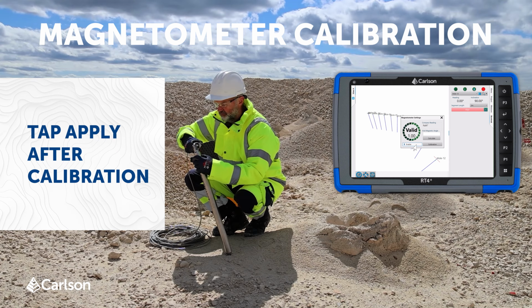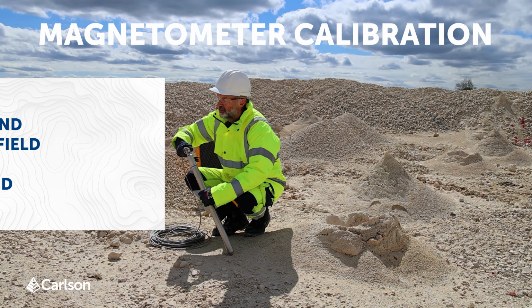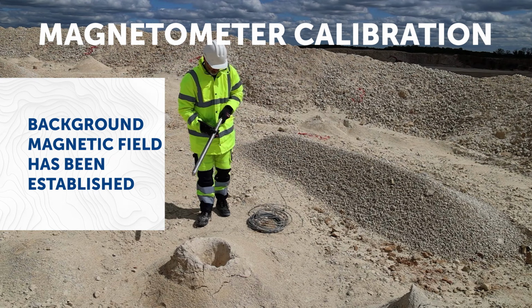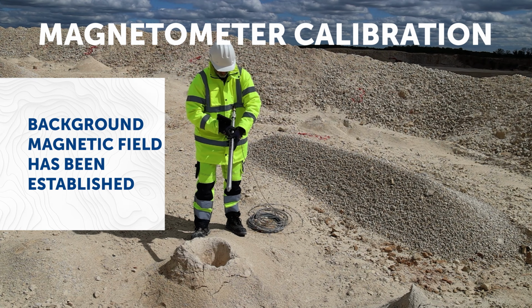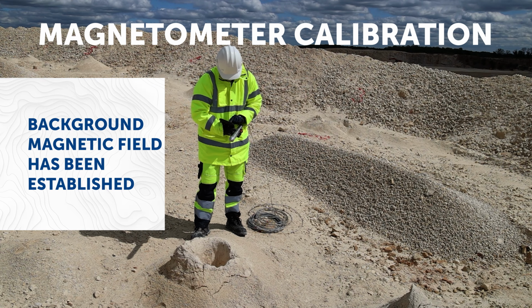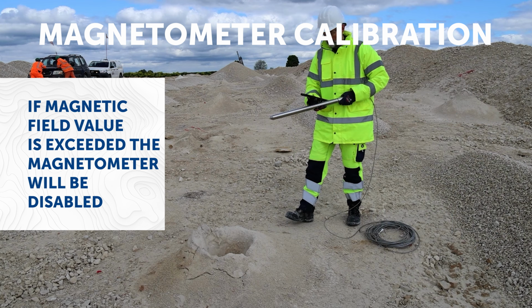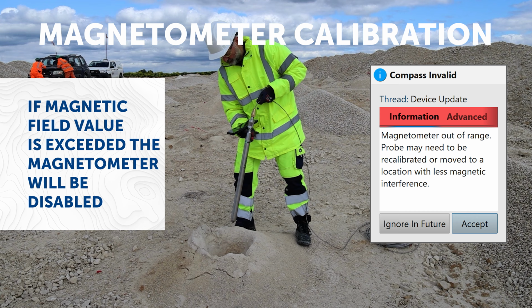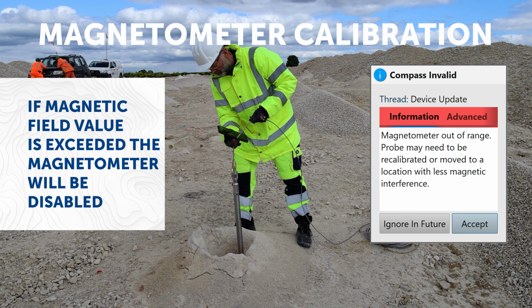A baseline level of the background magnetic field is now established and will be used to monitor the local magnetic field around the probe during all operations when the magnetometer is enabled. If the local magnetic field differs from the baseline by a set threshold, the magnetometer is temporarily disabled and you'll see a warning.